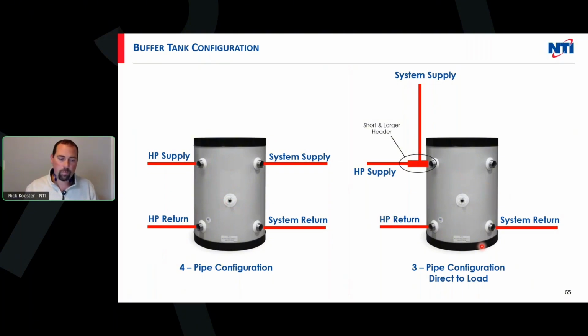We call this a direct to load configuration. The only main difference here is that instead of bringing my system supply off at a 4th port here, I'm going to create what we call a short large header off the front tapping of this tank, and I'm going to have the heat pump supply come in, and I'm going to go out to my system supply. And what that's going to do is guarantee I'm going to have the hottest temperatures or the coolest temperatures, depending on the mode, coming from my heat pump and going directly out to my emitter. So what happens with a 3-pipe is I don't necessarily blend as much here. Whereas with a 4-pipe, I bring in some hot temp here, I bring in cool return water here.